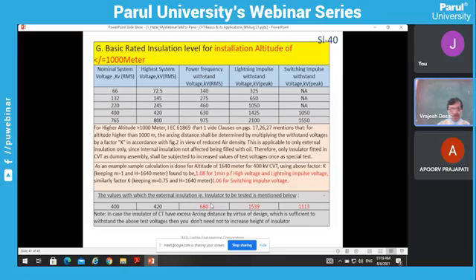There is one example that has been calculated. For 1640 meter, the altitude factor has been calculated, and for that purpose we have to test this insulator at 680 kV instead of 630 kV, and for lightning impulse 1539 kV peak in place of 1425 kV. Like that, switching impulse is to be tested at 1113 kV instead of 1050 kV.